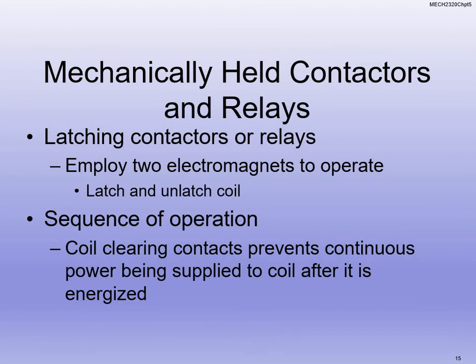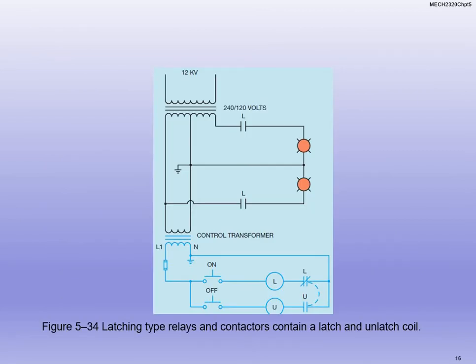We can have mechanically held contactors — we can latch them using electromagnetics with latch and unlatch coils. Latch means a kind of memory place — we talked about SR latches in electronics. We use latches for memory, holding something in place until we release the power or after power has been released for a certain amount of time. We can also use sequencing operation, which prevents continuous power from being supplied to the coil after it's energized — similar to the seal-in logic we did in PLC class. A latching relay has latch and unlatch with opposite contactors: one normally closed and one normally open.